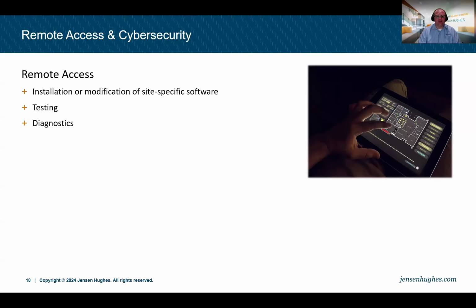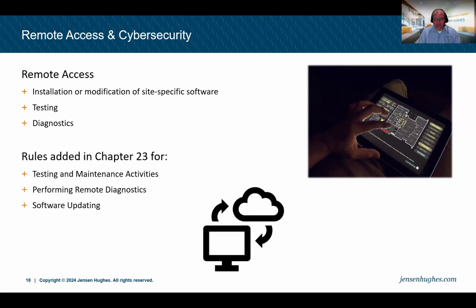And so remote devices include things like laptop computers, right? Cellular handheld devices, cloud-based systems, applications, all kinds of similar equipment and software is being provided in today's world. Now, some requirements have been added to the code, specifically in Chapter 23, if we're using remote access for testing and maintenance activities, performing remote diagnostics, and for updating any kind of software. There are a few rules that go along with this, including manually terminating the remote access at the remote device and at the fire alarm control unit. The access must be terminated after 1 hour of inactivity, so someone's not keeping a system connected for long periods of time. You need qualified personnel on site to activate software via a password. And if the software is changed remotely, the testing requirements of NFPA 72 remain the same.